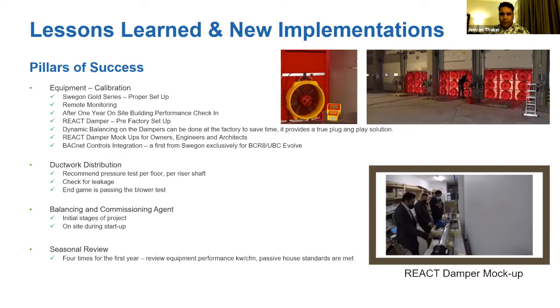React Damper, we talked a little bit about that earlier. A great example is we preset our values at the factory. The commissioning agent on this job had 2 weeks to do commissioning. There were 24 suites, so we had 2 React dampers per suite, so that's 48 dampers. He had 2 weeks to set that up and balance it. It took them 3 days to complete the whole project. So the commissioning side went down to, everybody's happy, right? Get off the project easier and get it up and running into the owner's hands.